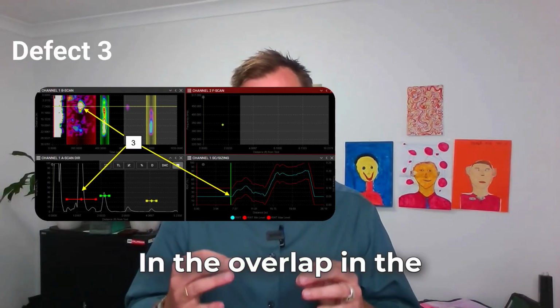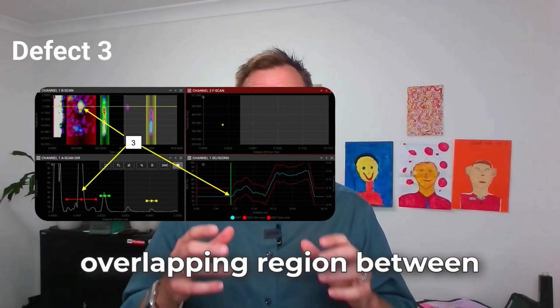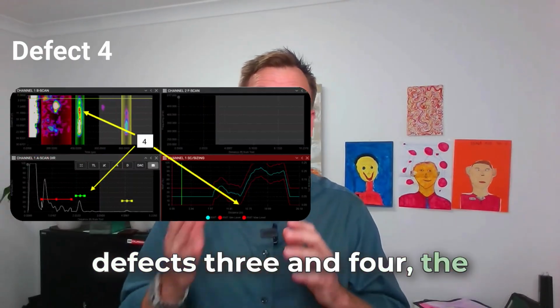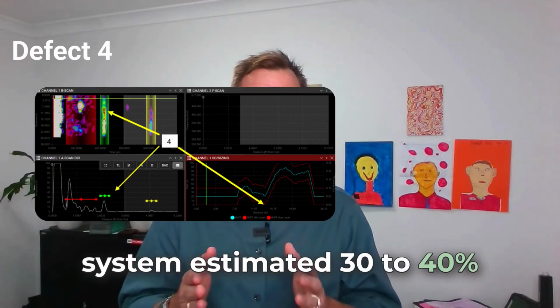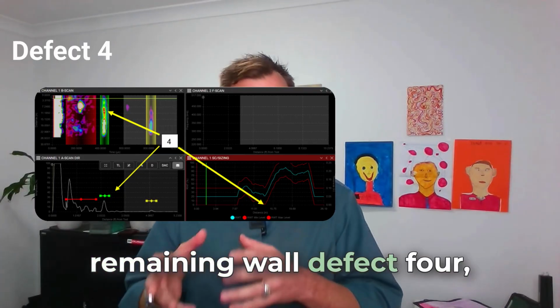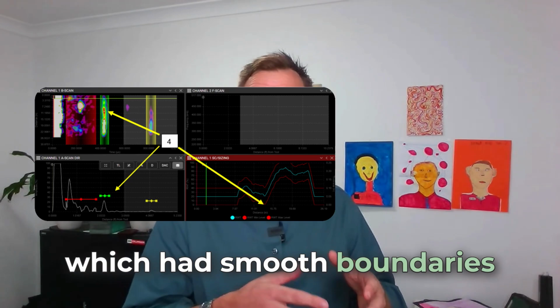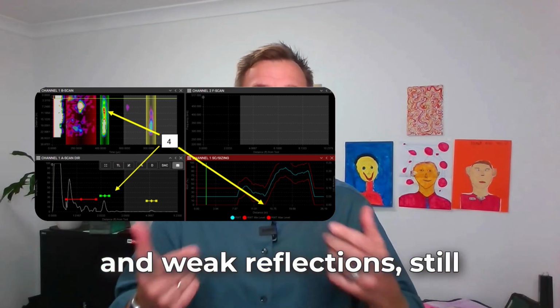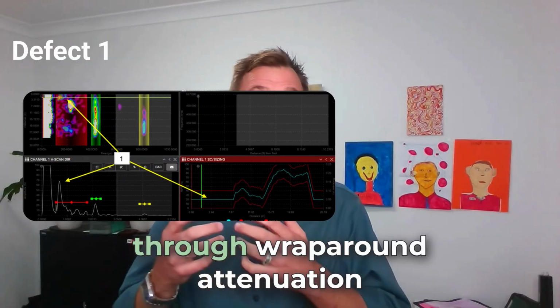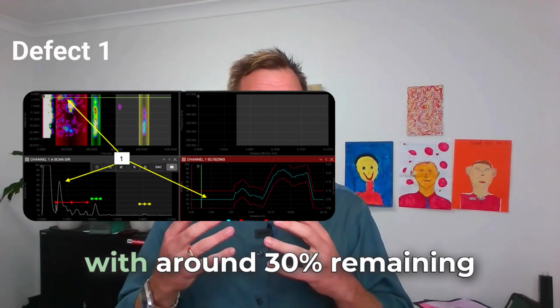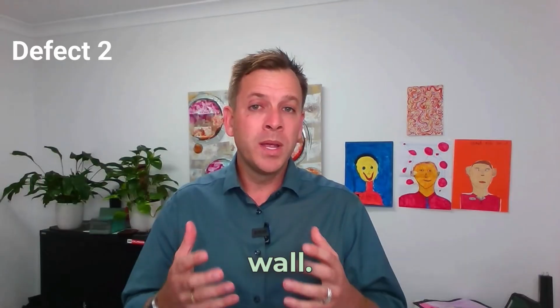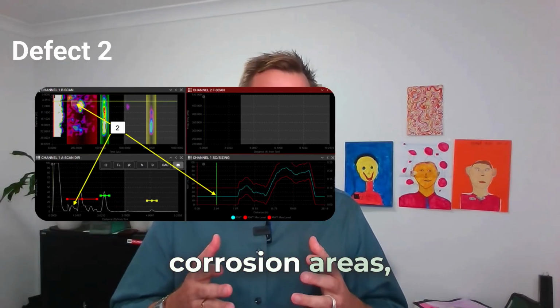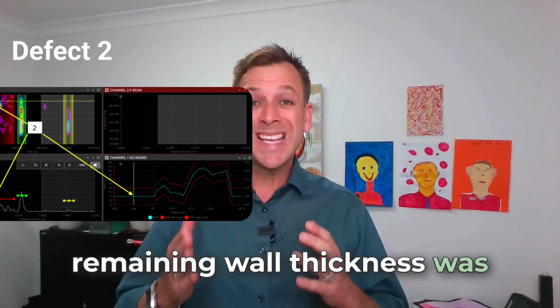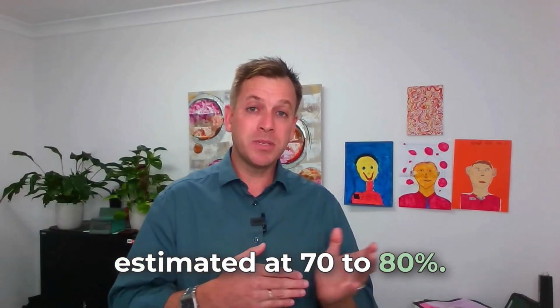In the overlapping region between defects 3 and 4, the system estimated 30 to 40% remaining wall. Defect 4, which had smooth boundaries and weak reflections, still produced a clear response through wraparound attenuation, with around 30% remaining wall. And across the general corrosion areas, remaining wall thickness was estimated at 70 to 80%.